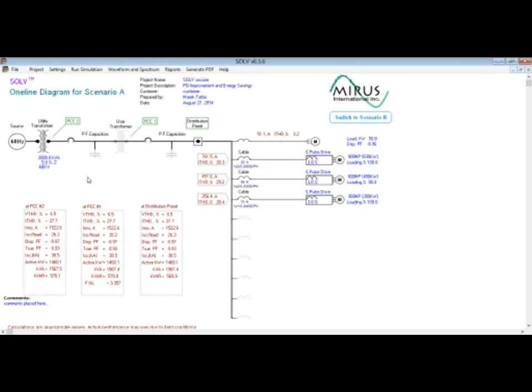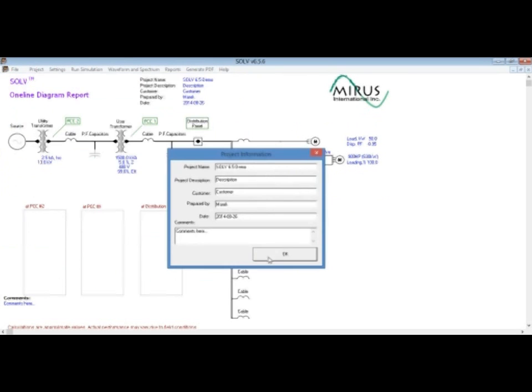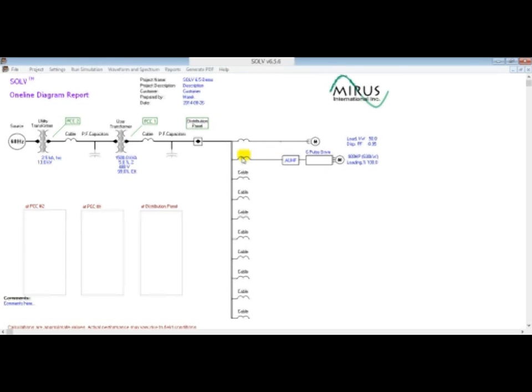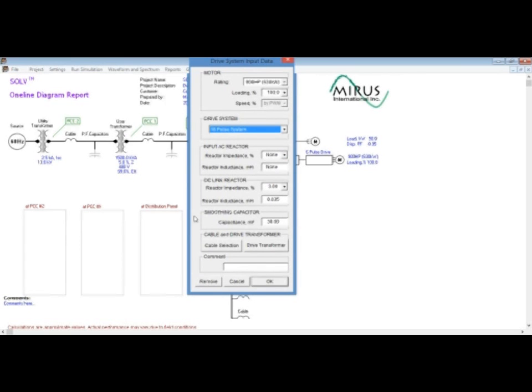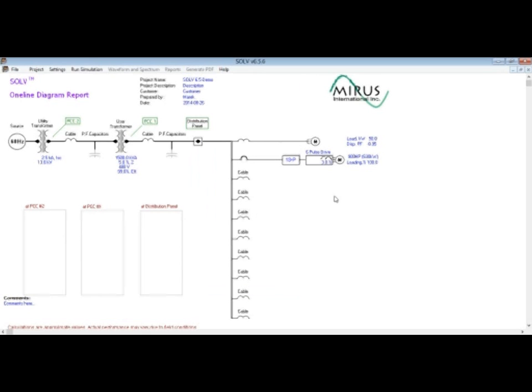Okay, more questions showed up. Can you go back to the other example and look at the 18-pulse scenario? In that example, 18-pulse is in series with a 6-pulse drive. Is this configured properly? This was my original question. Okay, so let me try to open that file and change this to 18-pulse. Okay, I know what you mean. This says 6-pulse drive here, but this is 18-pulse. So basically that label here is incorrect. The whole solution here, the 900 horsepower drive, is an 18-pulse solution, despite the fact that the label here says 6-pulse.